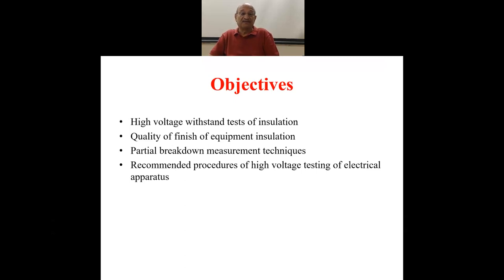But in no case, when you apply higher voltage, should any damage be caused to the insulation, or any damage be initiated in the process by applying higher voltage. That has to be ensured, and that is a question of experience, a question of quality of the insulation, quality of finish, that no damage to the insulation should occur, or no initiation of any damaging process, for example the treeing process in the case of solid dielectric, should be able to begin.